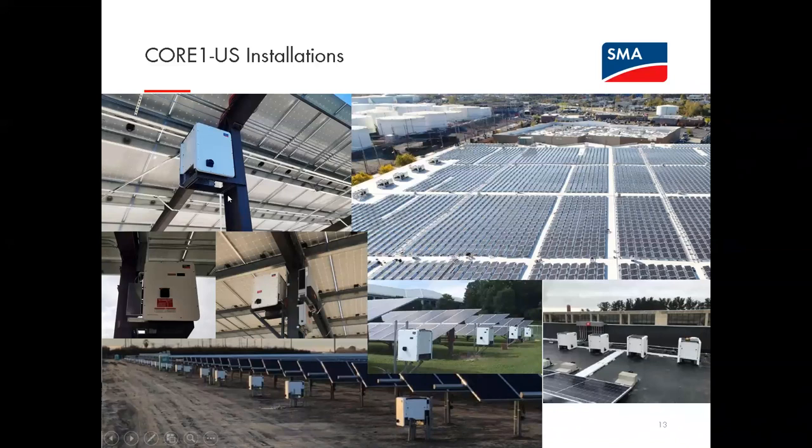that we very much like, because with this one you can see the thermal core of the inverter is up the center. So there are some heat sink fins that go into the center chimney of the inverter, and the thermal core allows for passive cooling, and then there are three speed control fans and a tray at the bottom that can turn on if the inverter warms up and force air over those heat sink fins. So we love that there's a good airflow path here up through the device.